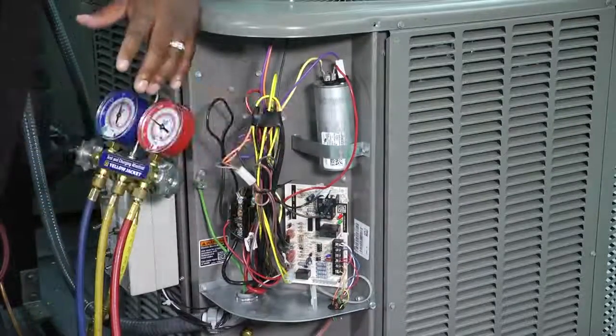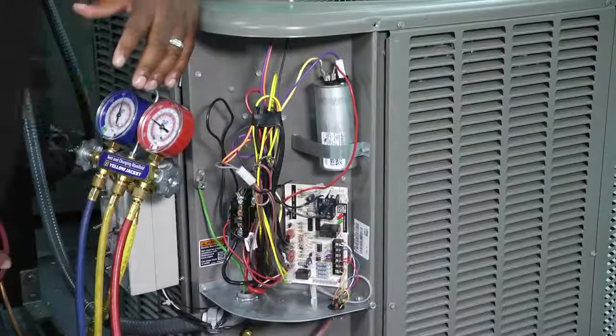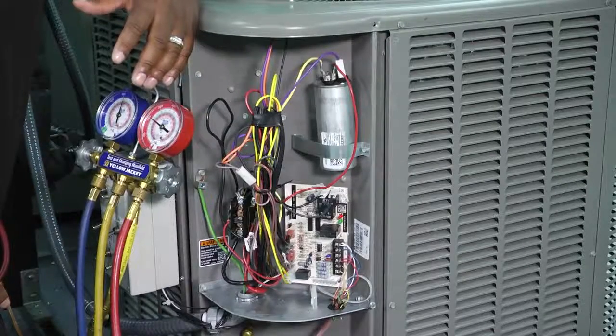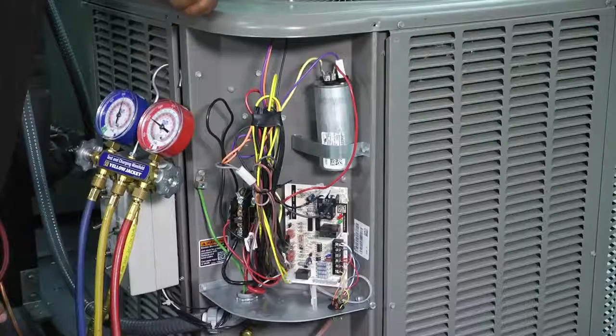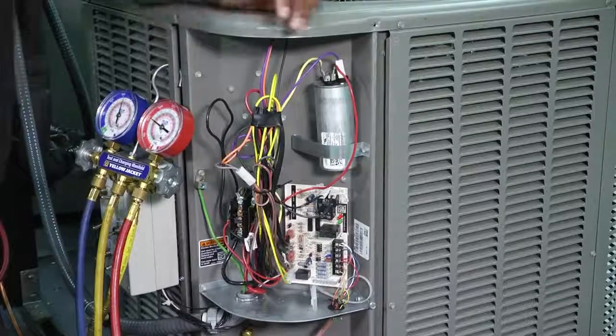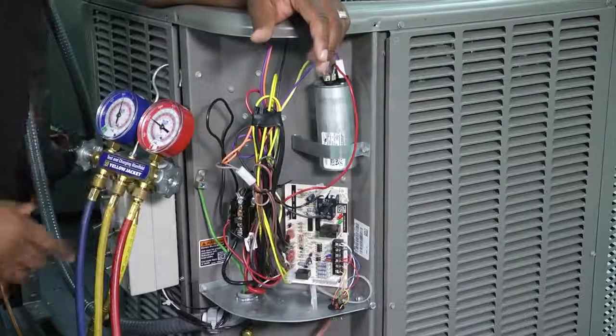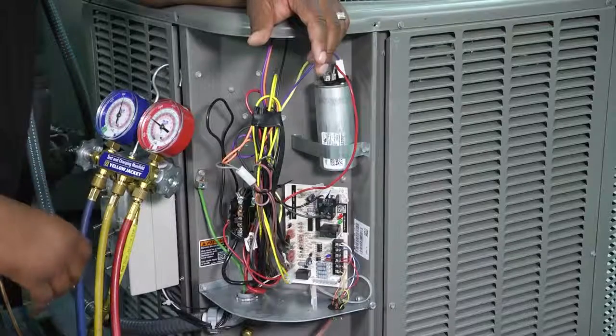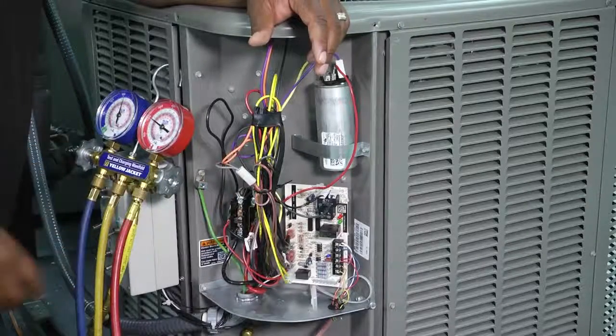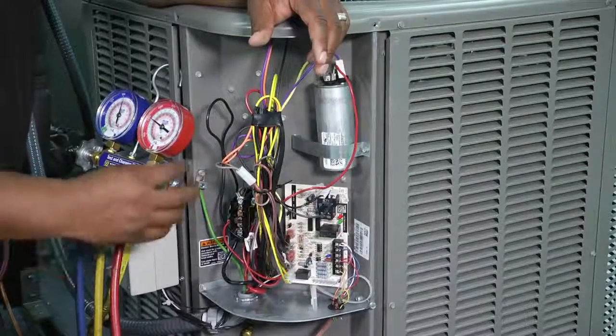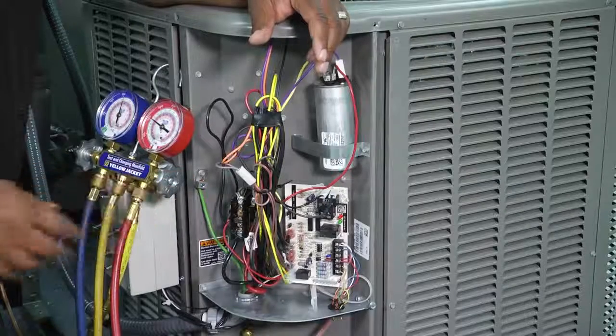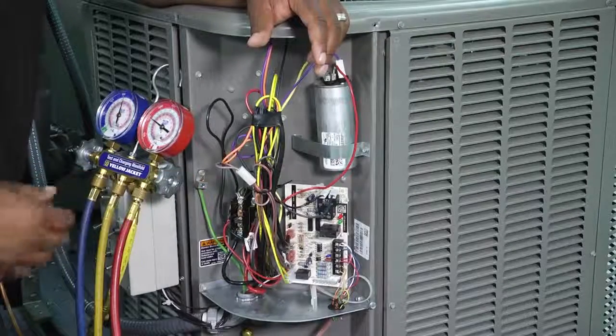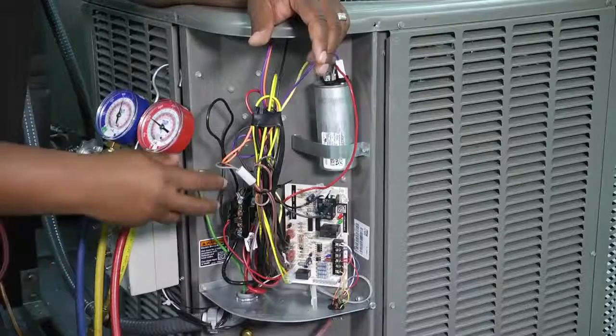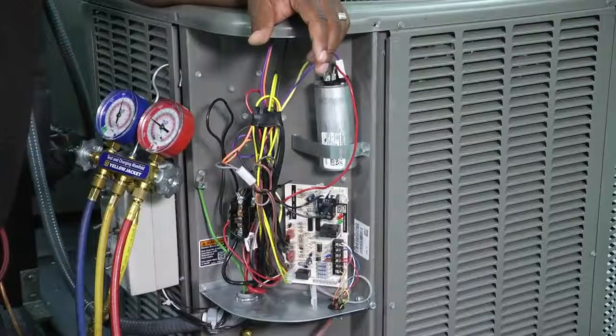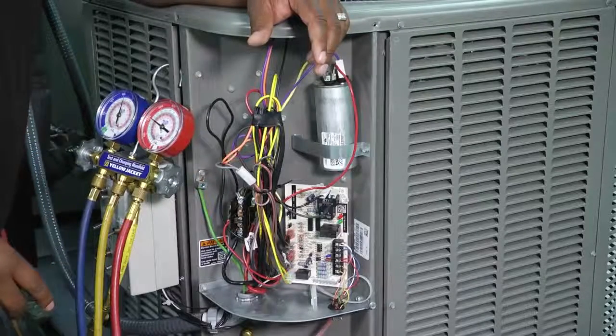So once we've checked the outside of that coil and got everything taken care of there, we have a couple other things inside of our unit that we also need to check. One of them is our contactor. Now, depending on what kind of contactor you have, the top part may be enclosed with a little shield to kind of prevent or keep things from getting out of there. Sometimes, I don't know why, but sometimes ants get collected in there and they could actually stop the contacts from making contact.